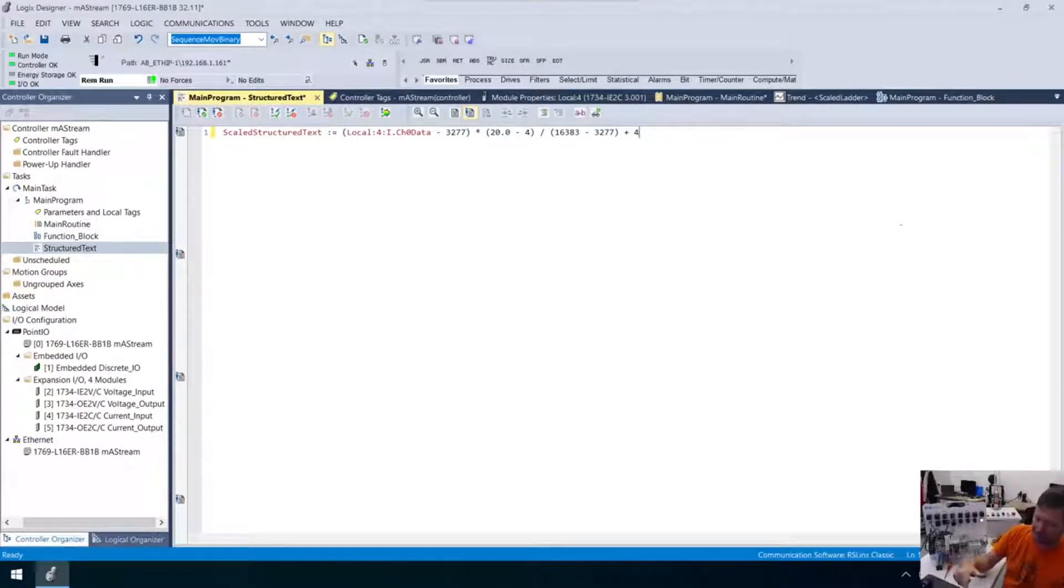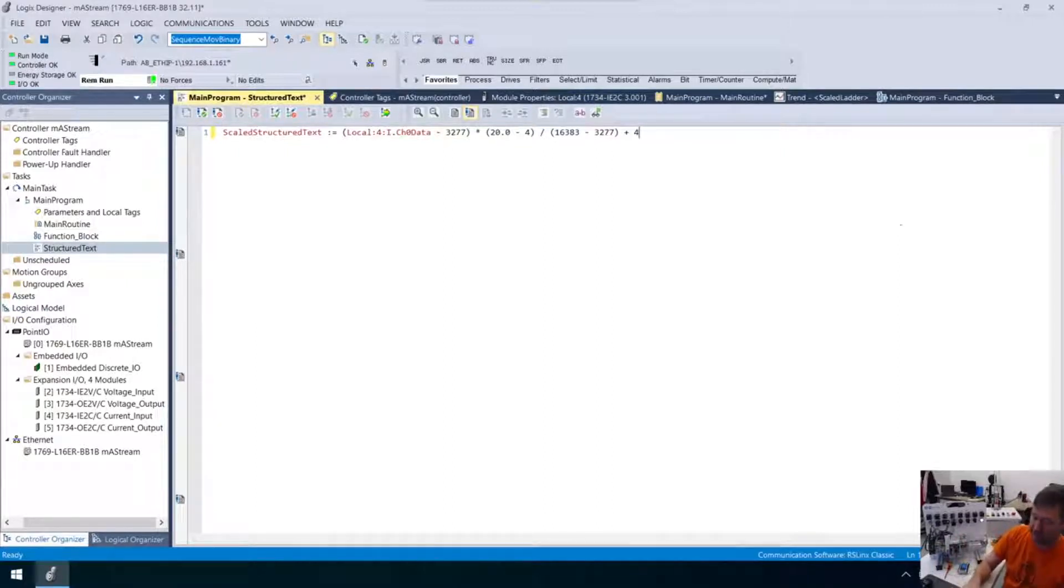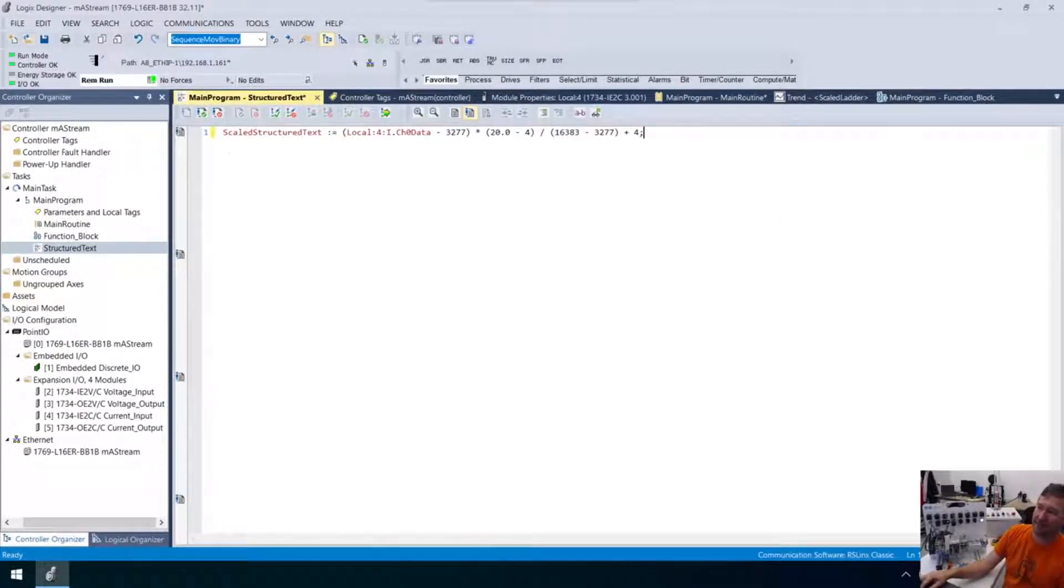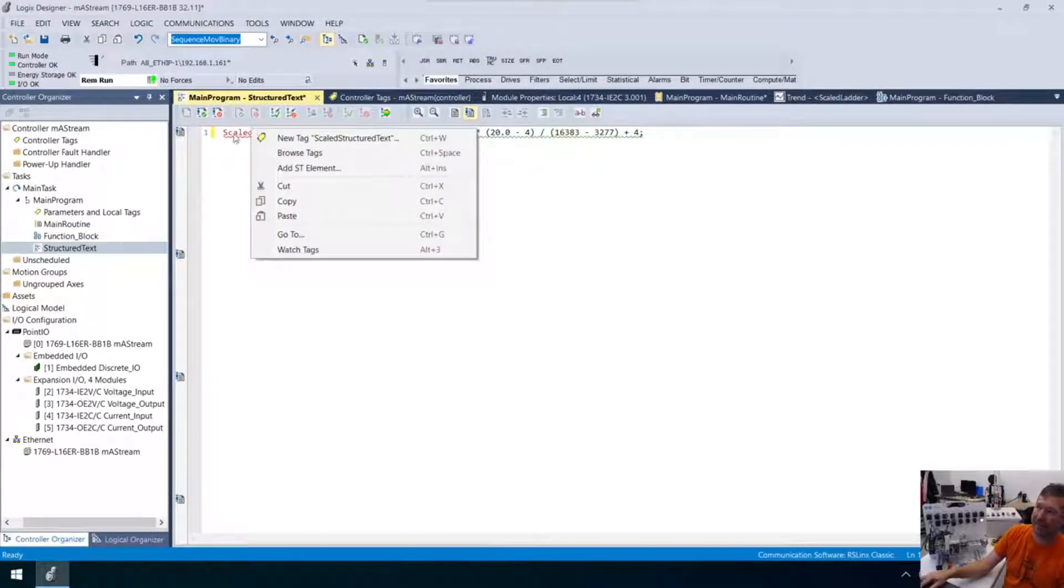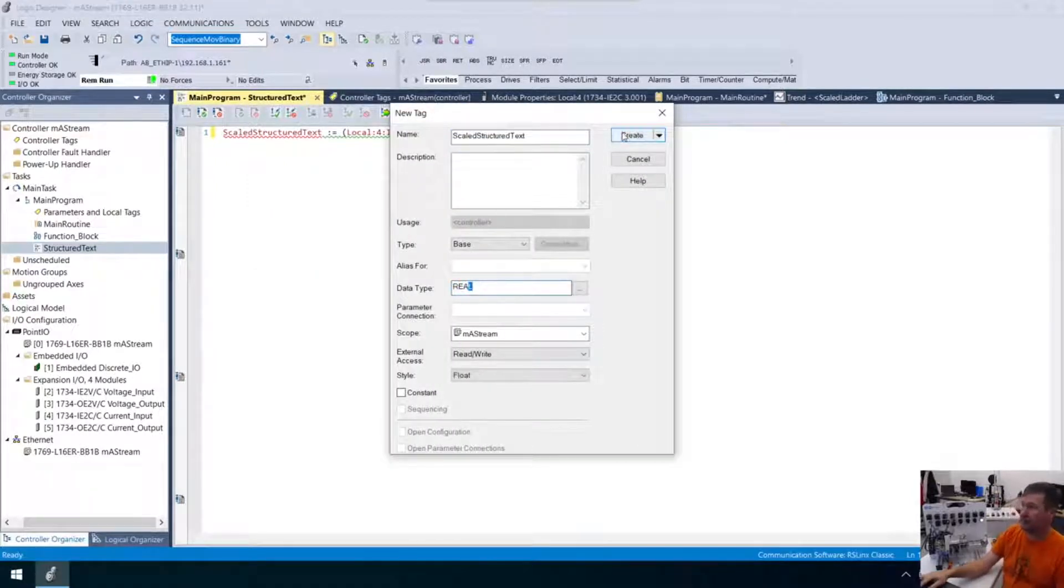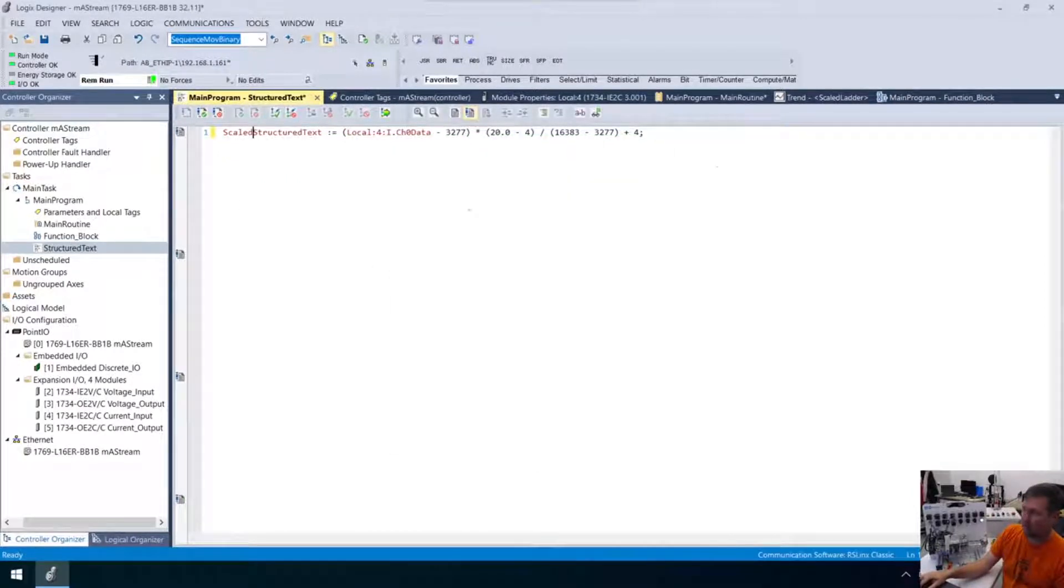That is exactly what is in our compute statement. And then here at the end of it, the only thing, and I forget this probably 75 to 90 percent of the time, is you've got to have a semicolon at the end of this. Now, the only thing is I just typed this, scaled structured text, and we need to right-click it, and it's new tag right there, just like we normally do in all the rest of them. Again, I'm going to make this one a real.